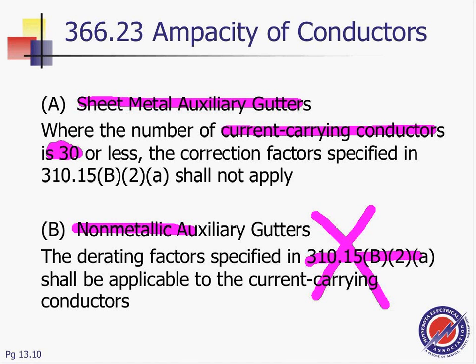If you go to the table, what is it? Table 310.15(B). You go to 310.15(B), and you lose a lot of amps if you put 20 of them, 50%. So if you have 20 conductors, or let's stay with 30. Say if I decided to put 30 hot, including neutral for harmonics. If I put 30, I'm cutting my amps to 45 amps.